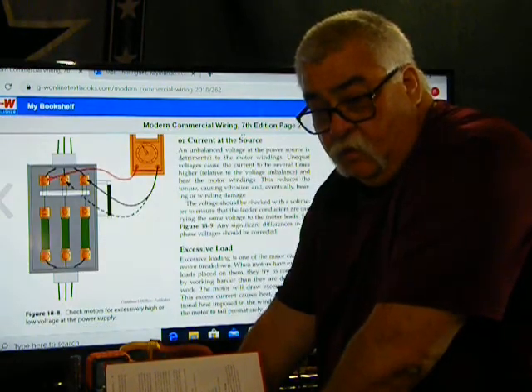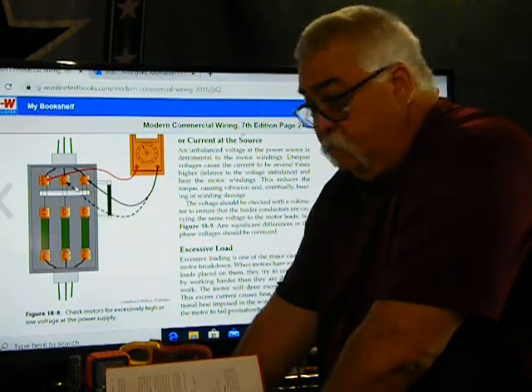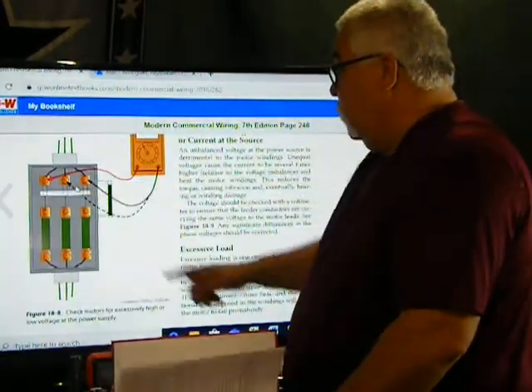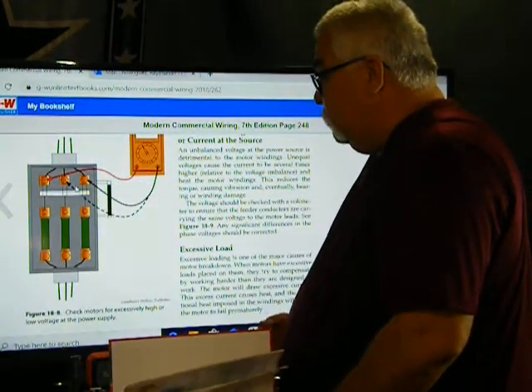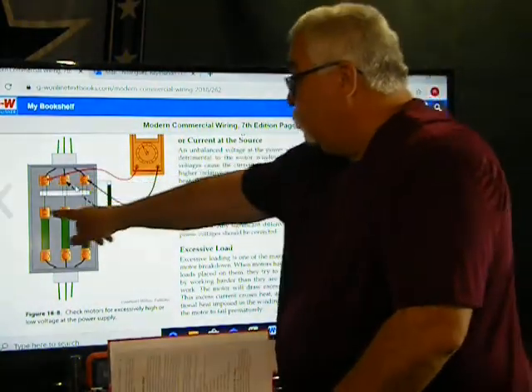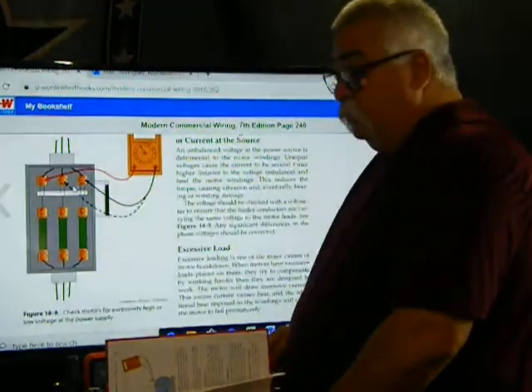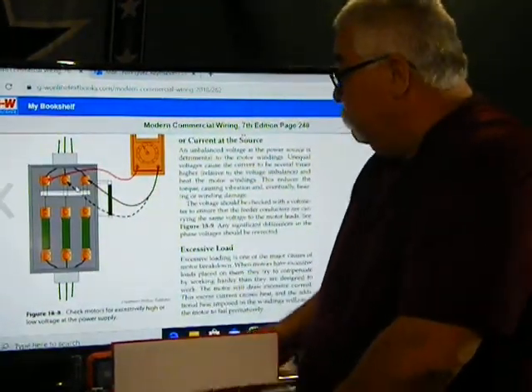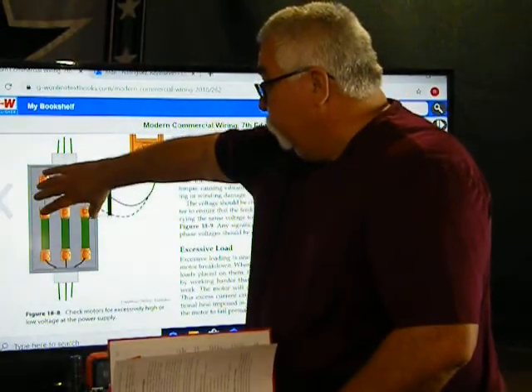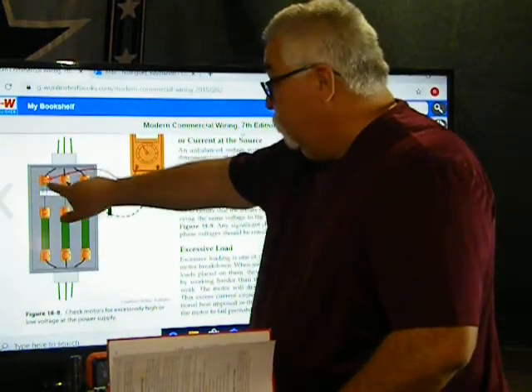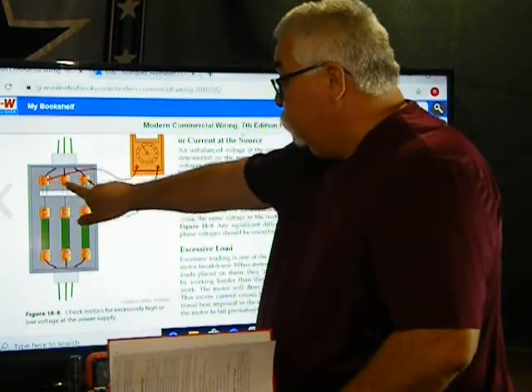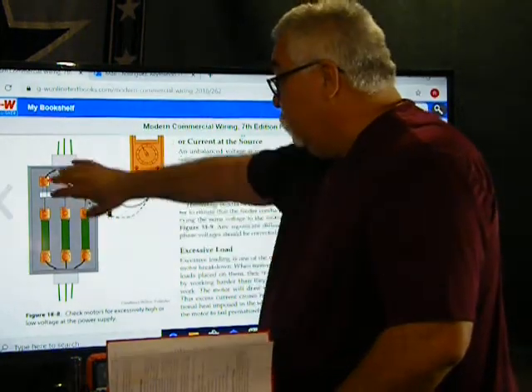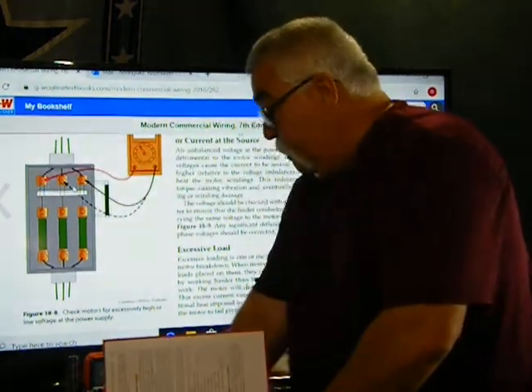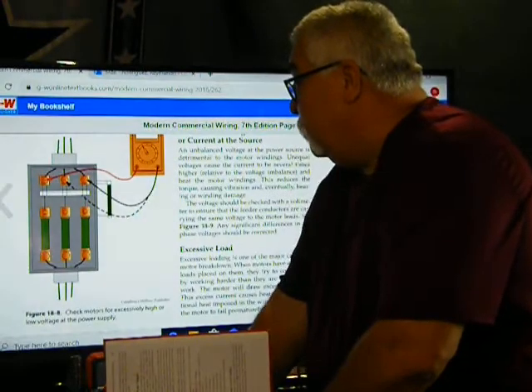There it is, where they're going to the line side. So now they're checking on the line side. Okay, so you can do it at the lugs, or you can do it at the individual fuses. It's up to you. Sometimes you have a cover that goes over this, so you can't see the fuse, but you can get to the lugs. Sometimes you can't get to the lugs, and you have to take that cover off. All right, let me go back here.